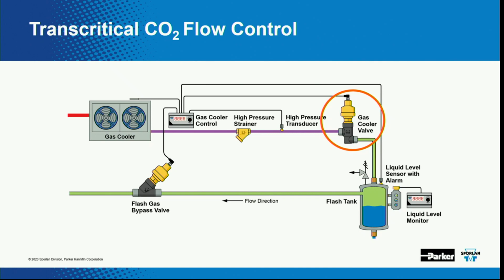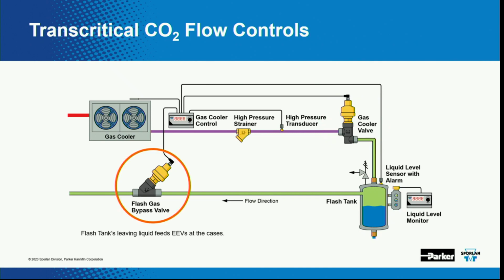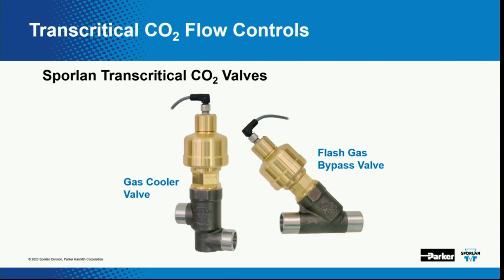So, okay, yeah, this is just showing what I just showed you. There's the gas cooler valve, there's the flash gas bypass valve, and there's what they look like in real life. So it's got our standard 42 millimeter digital linear actuator on top, and then it's got the stainless steel body for the high pressure. We've got these in a number of different sizes, and we're actually working on generating some new, some smaller sizes of these. I've been told that the gas cooler valve for a small application can also be used as a flash gas bypass valve, and I've also been told that an SDR can be used in the place of a flash gas bypass valve.